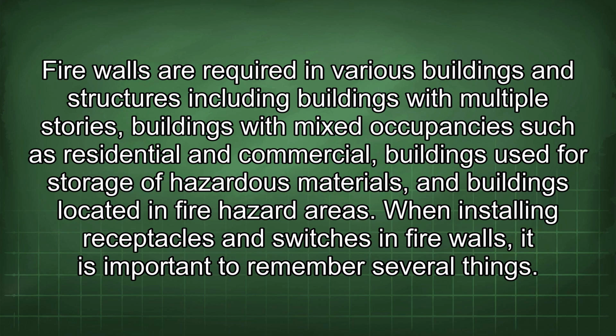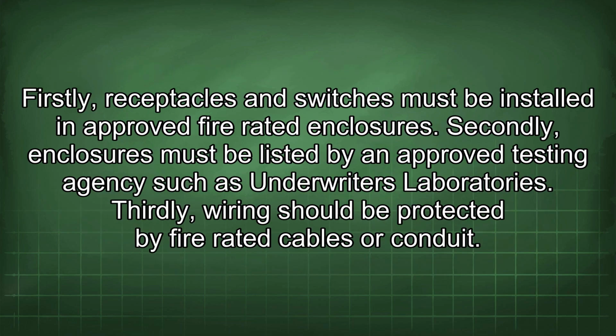When installing receptacles and switches in firewalls, it is important to remember several things. Firstly, receptacles and switches must be installed in approved fire-rated enclosures. Secondly, enclosures must be listed by an approved testing agency such as Underwriters Laboratories. Thirdly, wiring should be protected by fire-rated cables or conduit.